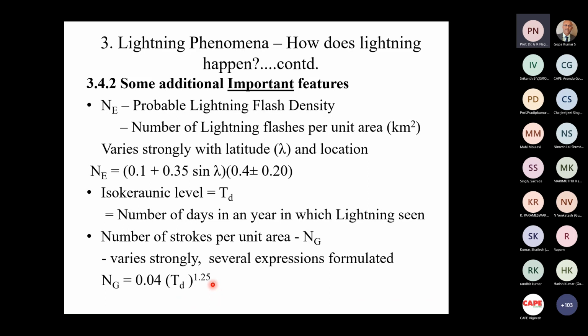So take Bengaluru, for example. For most areas in India, the isokeraunic level is about 30 to 40. If you take 40, that raised to the power of 1.25 becomes approximately 50 to 60, multiplied by 0.04 gives something like 3 to 4. So according to this relationship, about 3 to 4 lightning flashes can occur to the ground per square kilometer in a year. But with the statistical variation, it can range from 1 to 6, so if it happens to be nil in a given year, we need not be surprised.